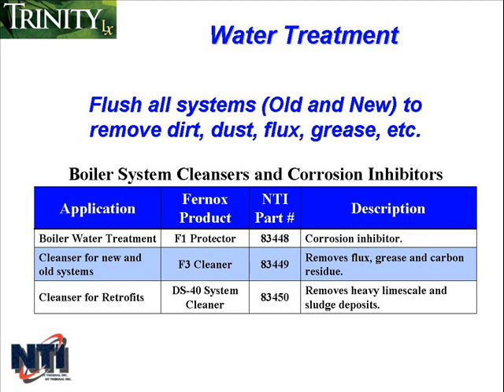For retrofits, all system piping including radiators must be cleansed of all buildup of sludge and scale. So all systems, old and new, need to be cleansed to remove flux, grease, and carbon residue. NTI recommends cleansing the boiler system with Fernox F3 cleaner. For retrofit applications with heavy limescale and sludge deposits, you may need a heavier duty cleaner. It's important to properly cleanse the system because failure to get rid of the heating system contaminants may void your NTI warranty and could result in premature heat exchanger failure and/or property damage.